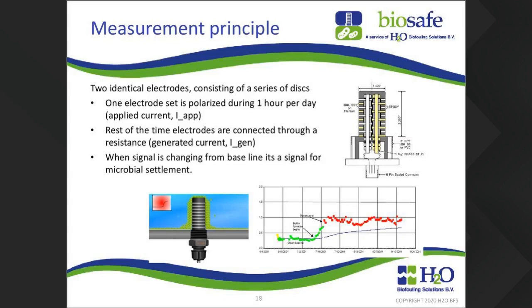So when the signal is changing from baseline, there is a signal of microbial settlement, as you see in the graph, and the probe can provide an alarm function, which will change the signal into a different color, red, as seen in the graph. So when there is a red signal, you know there is a biofilm present in your cooling water system.